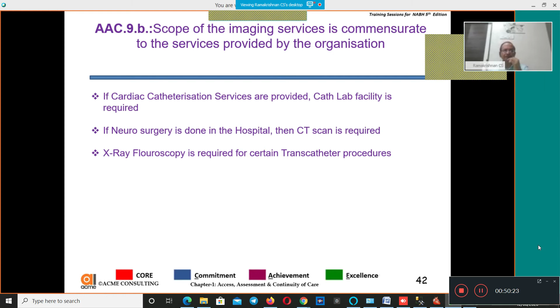Again, on infrastructure, there should be a radiation protection zone to prevent scattered radiation from affecting the patients. Today, we talk about AERB approvals. AERB provides approval for siting the equipment. There are three levels at which AERB comes into the picture. One is the equipment: whatever you are buying should have a type approval certificate from the Atomic Energy Regulatory Board. That means it meets mandatory exposure limits and all. This is done by the manufacturer of the equipment. While manufacturing each batch of the typical equipment, he needs to get approval and a certificate called a type approval, which confirms it meets mandatory exposure limits.